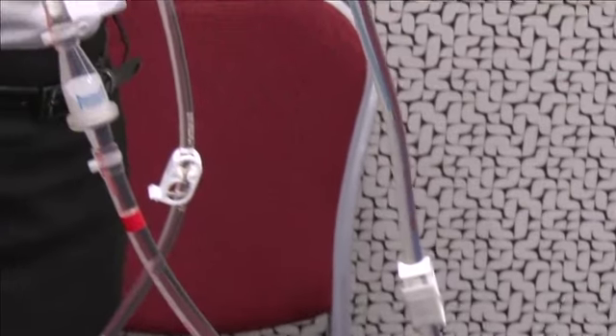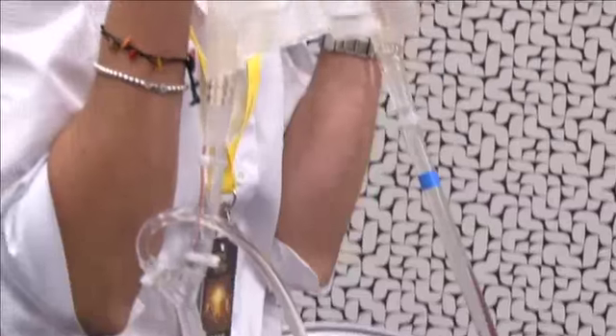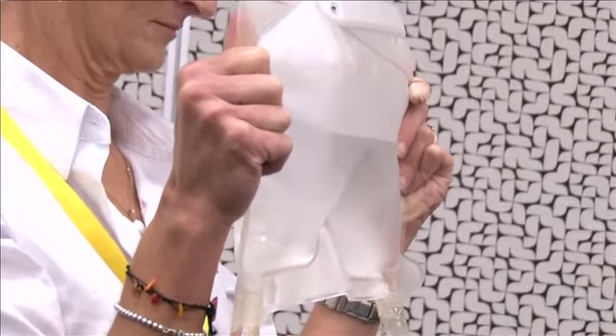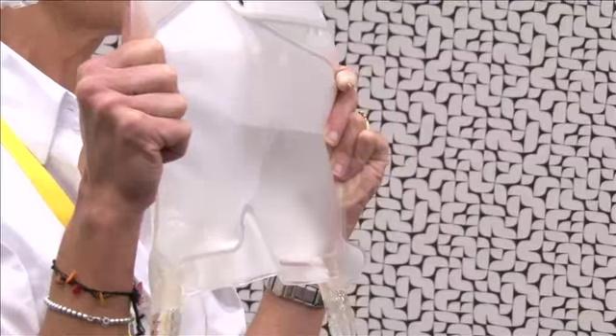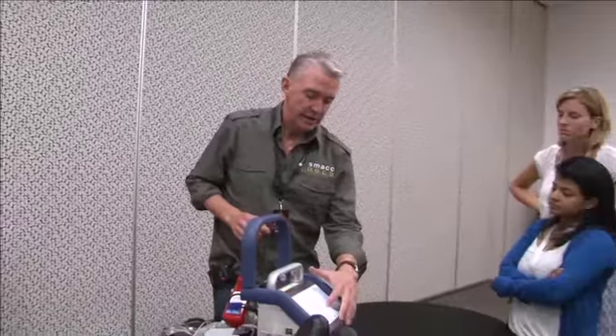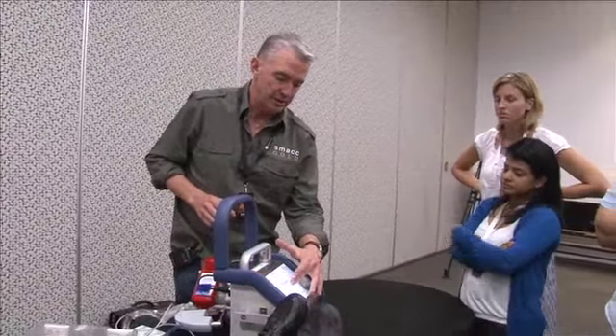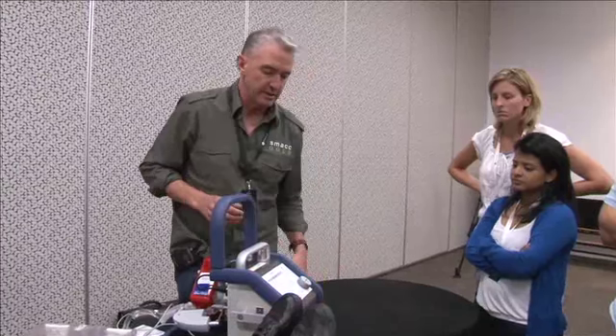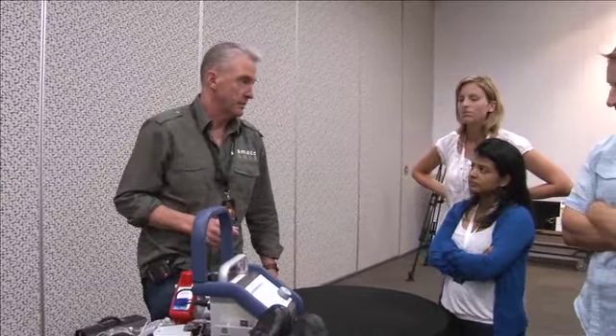So here's a bubble that's just been detected in the circuit, and as I said, the pump shouldn't stop in response to that because we don't want it to. And so in ECMO mode, with the various modes that can be selected for these pumps, we can clear that bubble and keep going.